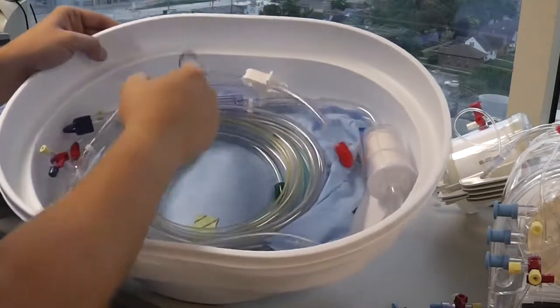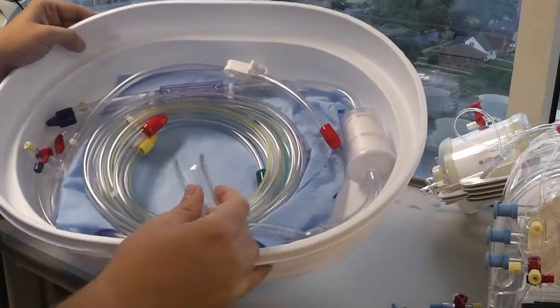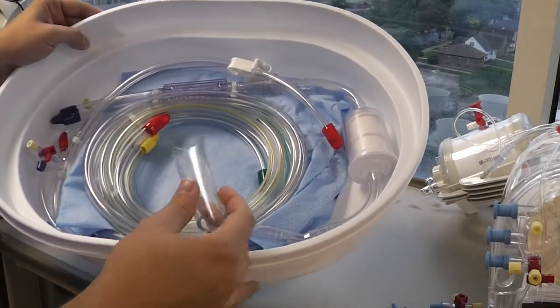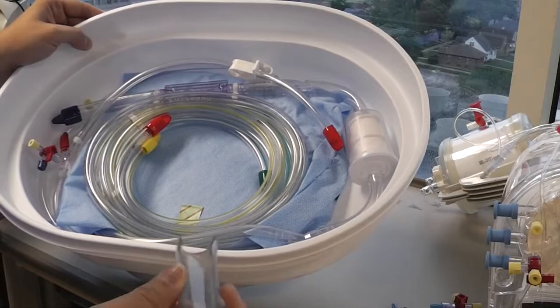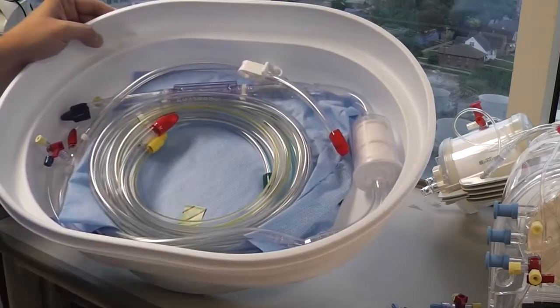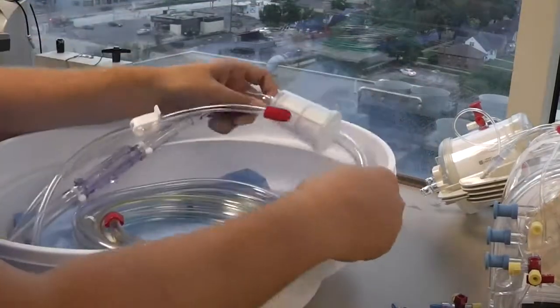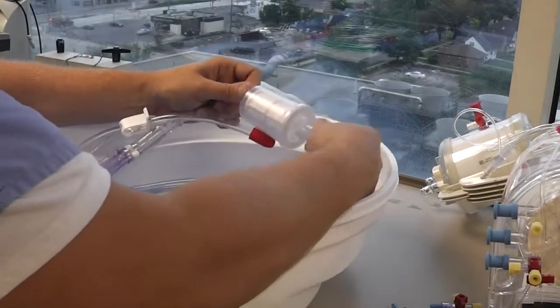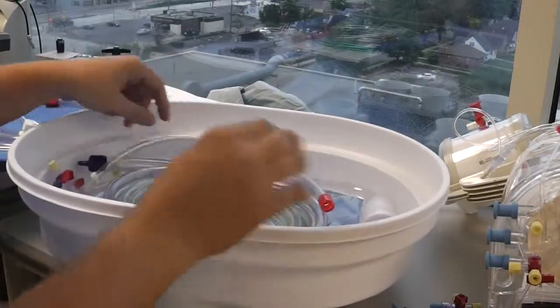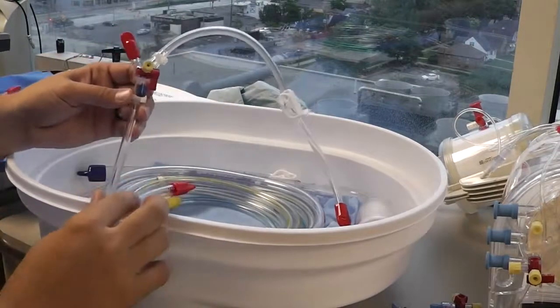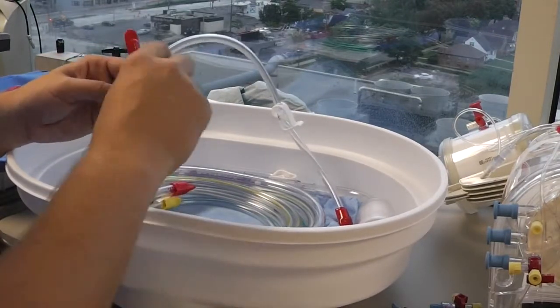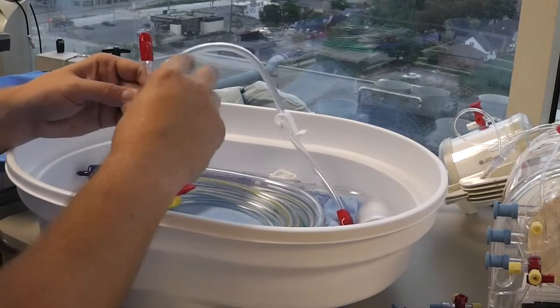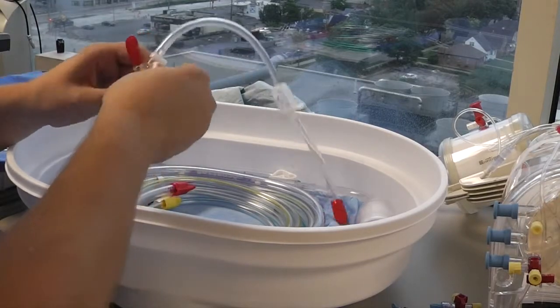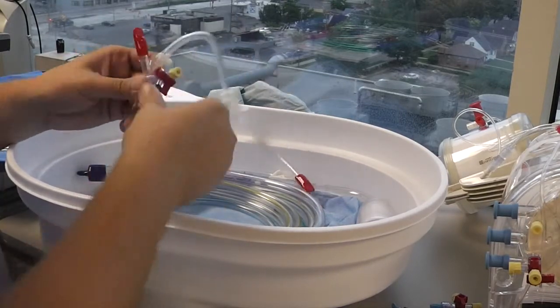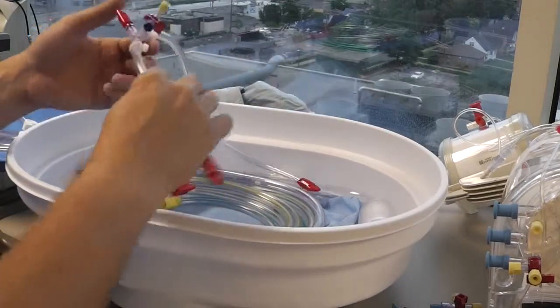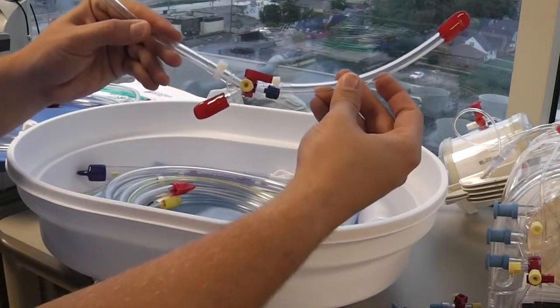We're just going to remove this little cover off of the venous sat and hematocrit sensor here on the venous return. We're going to tighten up these connections on the pre-bypass filter. We're going to check this stopcock on the recirc line. This is almost always loose. You can see that was loose. So we're going to just tighten that up. You want the stopcock facing you, so it's going to be oriented like that.